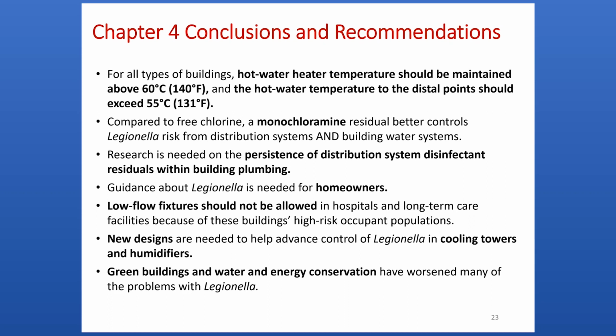A fifth important issue from this chapter is that low-flow fixtures should not be allowed in hospitals and long-term healthcare facilities. These fixtures are known to be very favorable for Legionella growth. They have low to no flow, water stagnates, and they have no disinfectant residual. Any temperature control you might have been trying to achieve will dissipate. They simply cannot be allowed in situations where high-risk occupants, like immunosuppressed people, could be exposed.